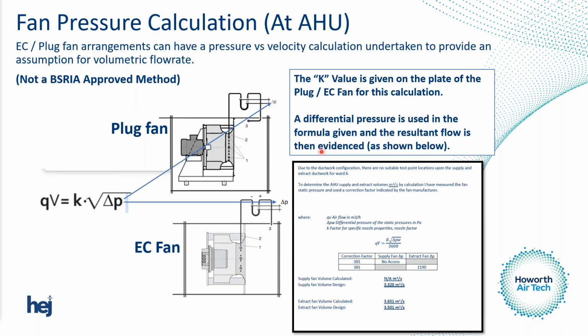And obviously there's other bits and pieces within the industry that we can look at, and there's new stuff coming into the industry all the time, and this is a fairly new method of assessing a flow rate coming down an air handling unit. Obviously, I'm guessing that most people on the call would be familiar with fan curves and assessments of fan curves within centrifugal fans or axial fans, whatever it might be. But these are the type of fans that we have now within air handling units. We have a plug fan, we have an EC fan. The EC stands for electronically commutated.